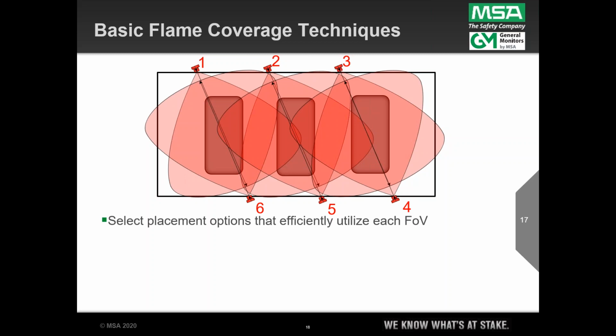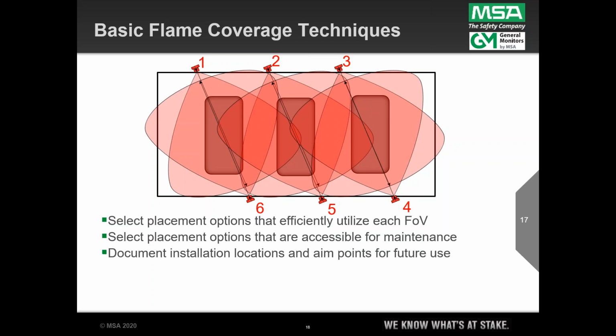And so here it is efficient utilization of the field of view. We can provide a degree of discrimination on each detector. There's still going to be some locations where two detectors might see it, but the bottom line is we've got each one covered as thoroughly as possible. We still have to look at obstructions and ducting and piping and so on, but by keeping the elevation at or just slightly above the top of that piece of equipment, we can make sure they're accessible for maintenance purposes. And then if I'm the technician on site, I'm going to have those install locations and aim points documented in my database for future use.